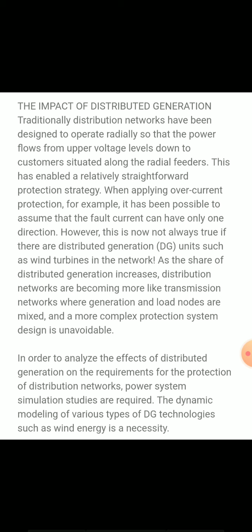Power system simulation and modeling studies have shown that distributed generation causes several challenges to the protection of distribution networks. Some of the problems are mentioned here: false tripping of feeders, nuisance tripping of production units, blinding of protection, increased or decreased fault levels, unwanted islanding, prohibition of automatic reclosing, and unsynchronized reclosing.